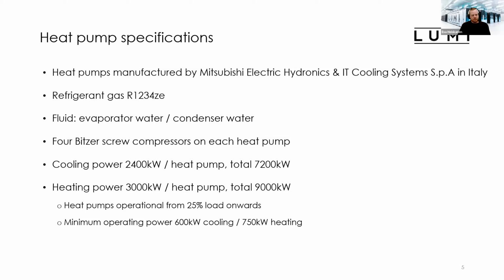Each heat pump has a 4 Bitzer screw compressors, and they have cooling power of 2.4 megawatt on each heat pump, which makes a total of 7.2 megawatts of cooling power, and heating power of 3 megawatts per heat pump, and a total of 9 megawatts of potential district heating and waste heat utilization. A single heat pump is operational approximately from 20% load onwards, so a reasonable operation power for a heat pump this size is 600 kilowatts of cooling, and it makes us 750 kilowatts of heating at that load.